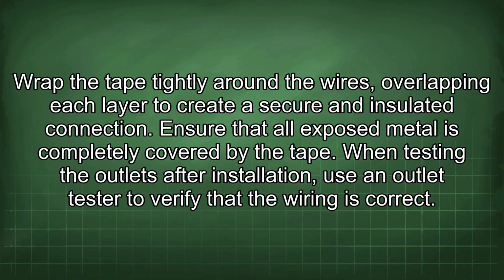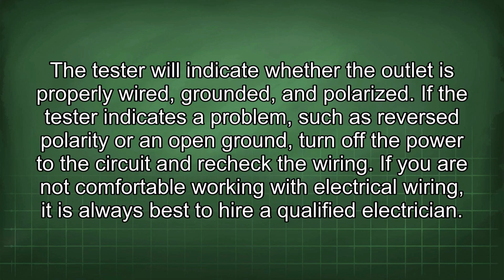When testing the outlets after installation, use an outlet tester to verify that the wiring is correct. The tester will indicate whether the outlet is properly wired, grounded, and polarized. If the tester indicates a problem, such as reversed polarity or an open ground, turn off the power to the circuit and recheck the wiring.